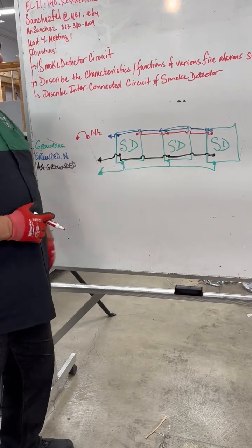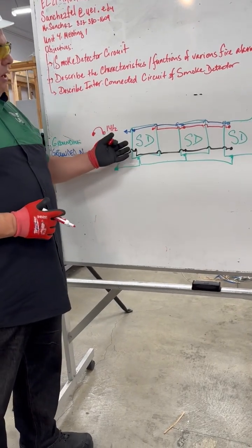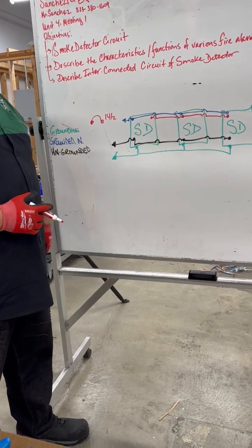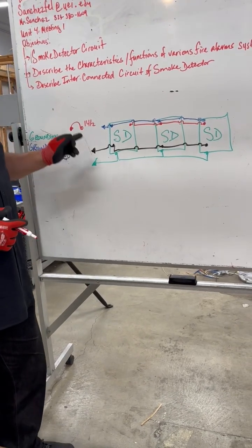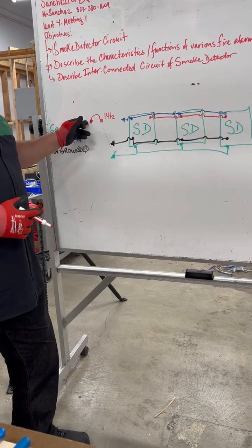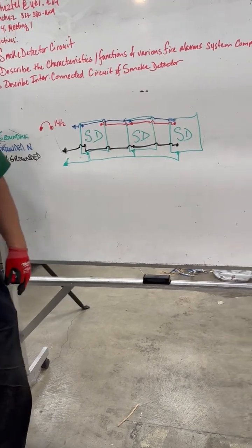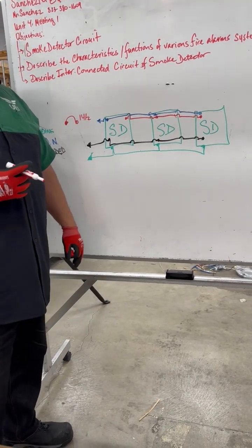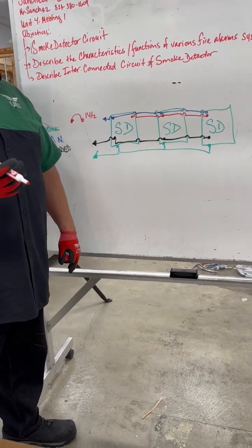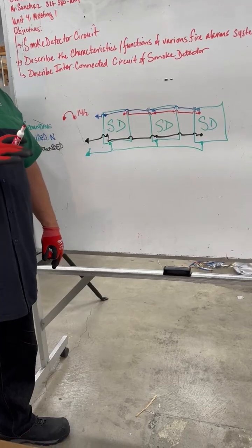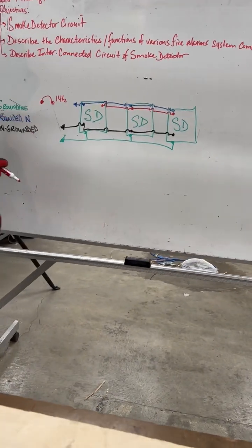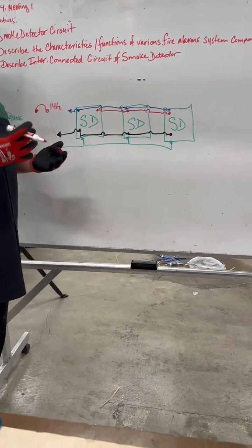I'm going to be using a 14-2 cable, bringing in power into that first smoke detector from the main circuit breaker that's dedicated to that. That one's going to be specifically labeled. I have seen in some installations where you can actually purchase a circuit breaker that is red in color, and it's specifically designed just for smoke detector fire systems. But other than that, a label works fine as well.